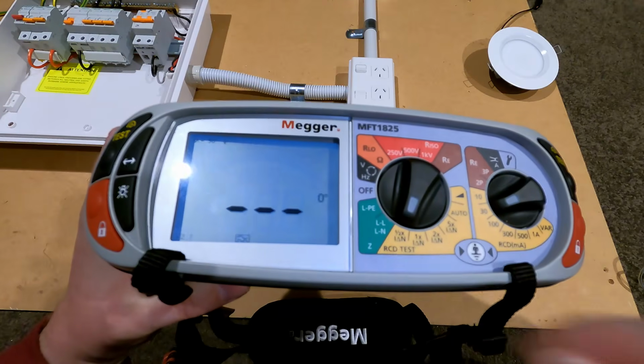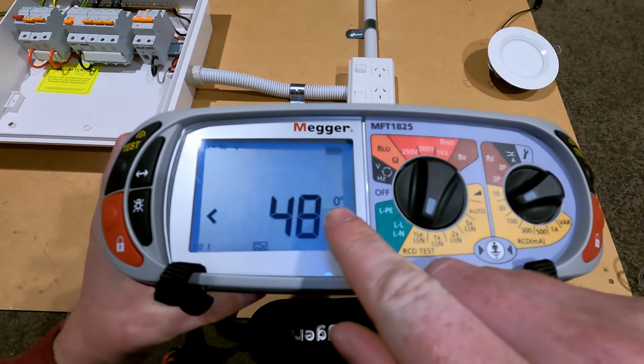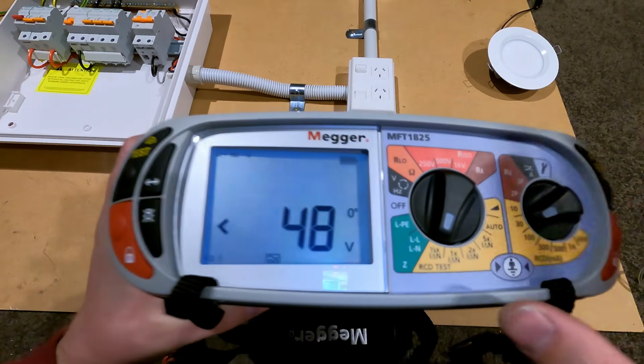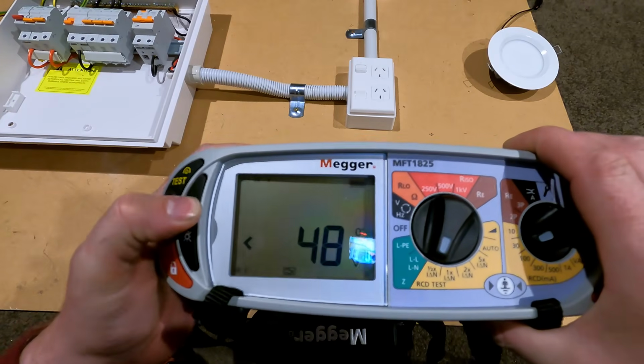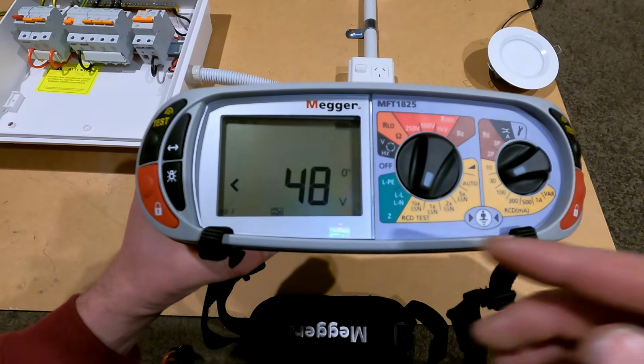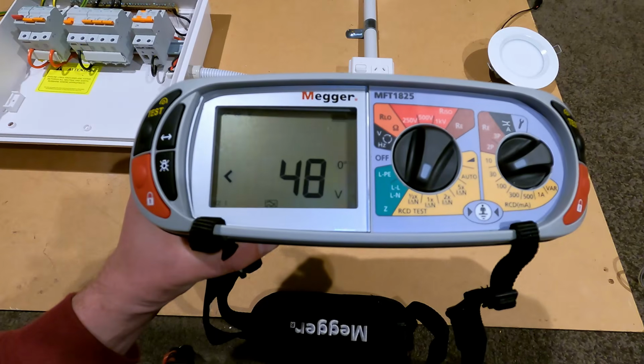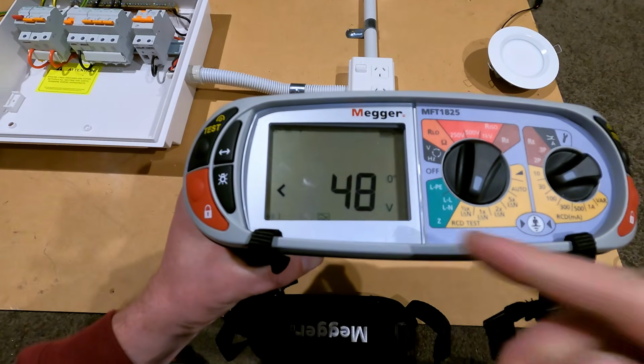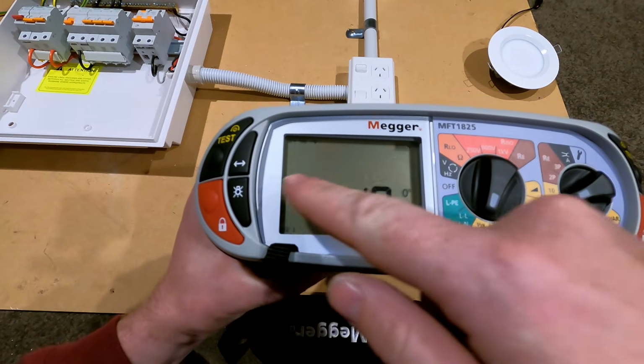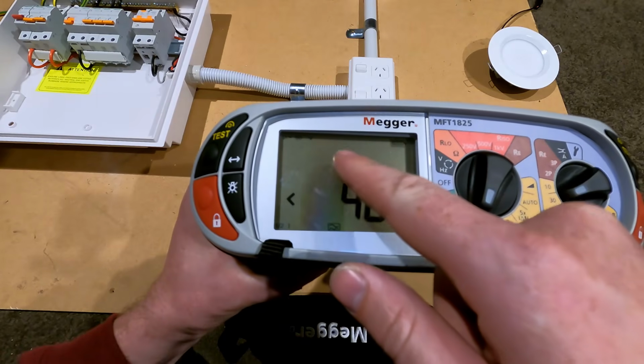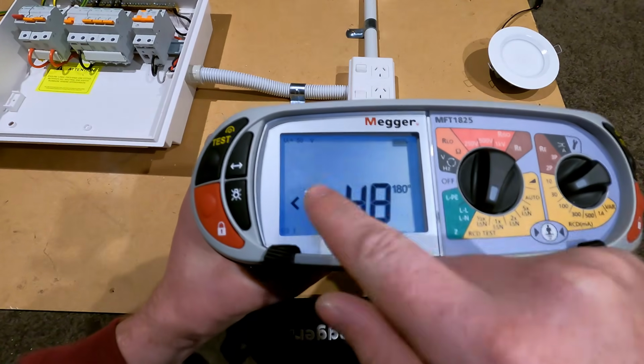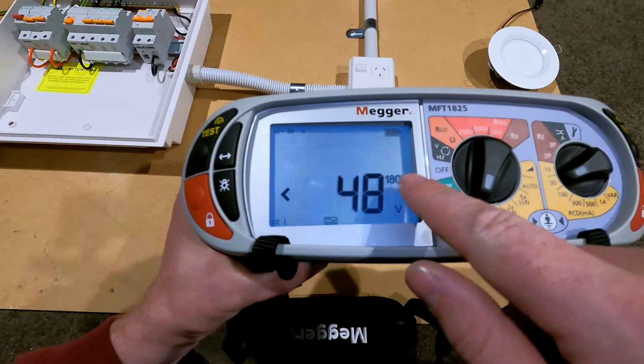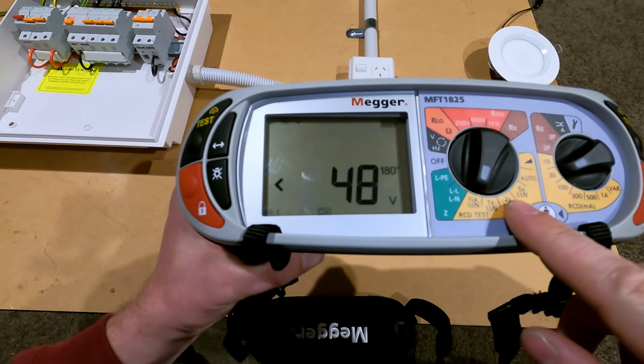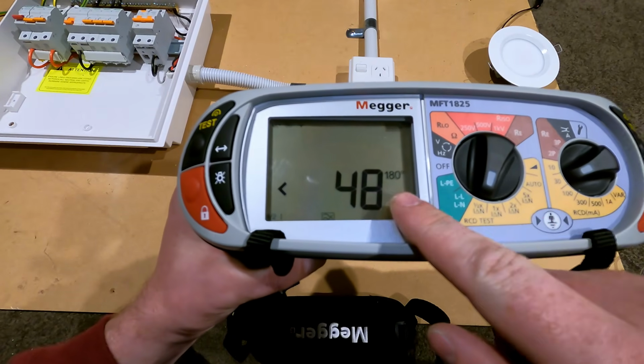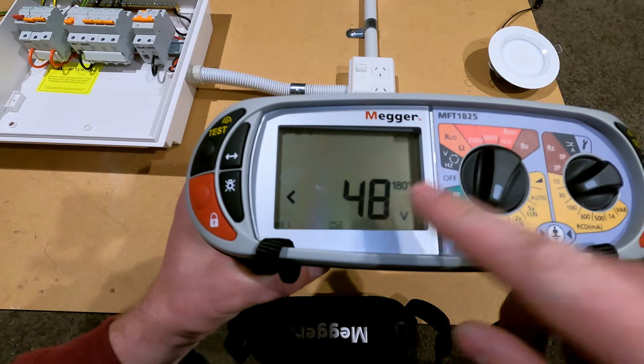So when you fire the RCD tests on, you'll notice a wee angle come up on here. Now you can switch between 0 degrees and 180 degrees. What these angles are, the 2 half cycles of your sinusoidal wave. So at 0 degrees here, you're going up on the positive cycle of the wave. And then at 180, you're now dipping into the negative side. You want to be testing each RCD test at both 0 and 180 degrees to get a proper test.